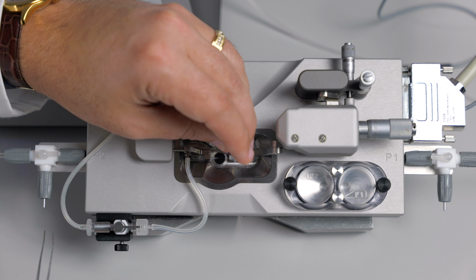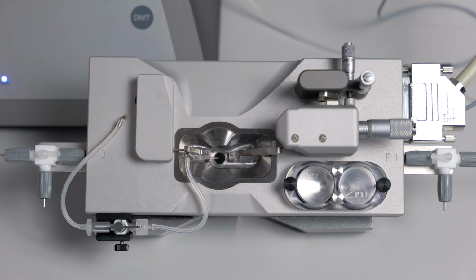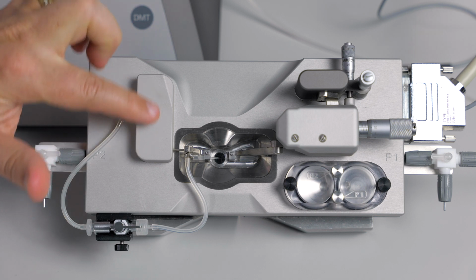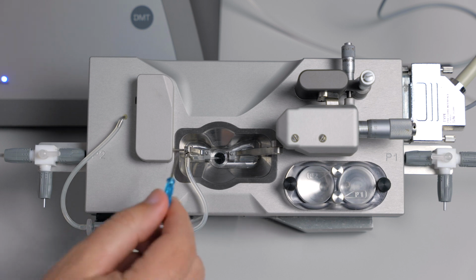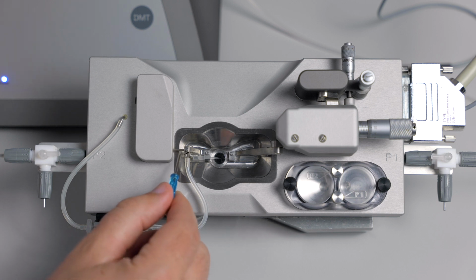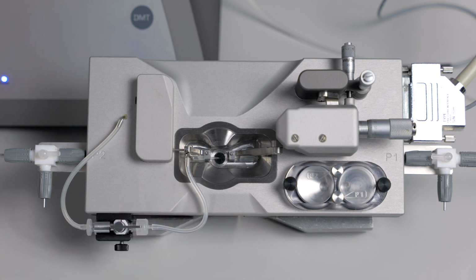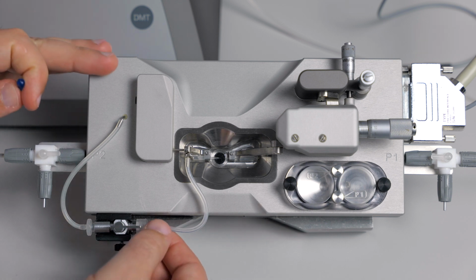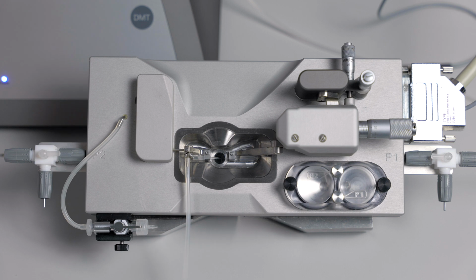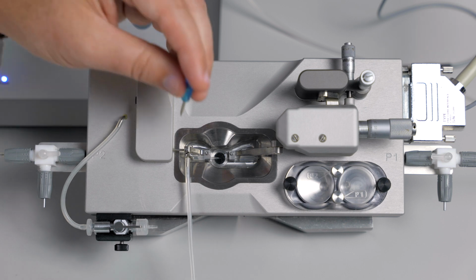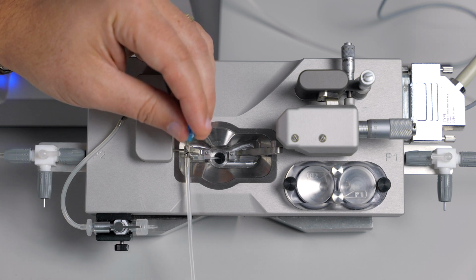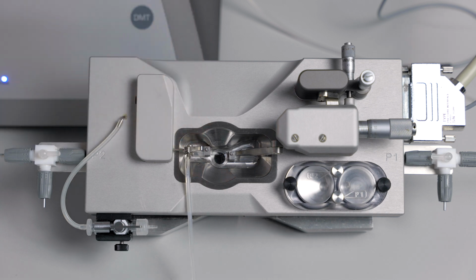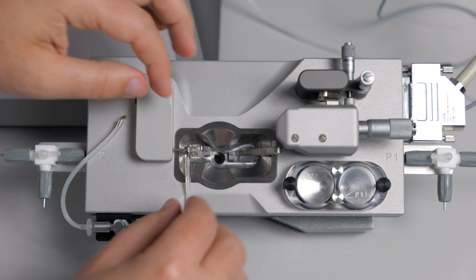The process is very similar on P2, but there are a couple differences. When making adjustments or replacements on the P2 side, you always need to be mindful of the force transducer. Anything connected to this arm can damage the force transducer. Therefore, we need to limit the amount of force used. Start by removing the tubing from the valve on the bottom of the P2 chamber. You will then loosen the screw on top of the arm from the force transducer. Now carefully remove this mount.